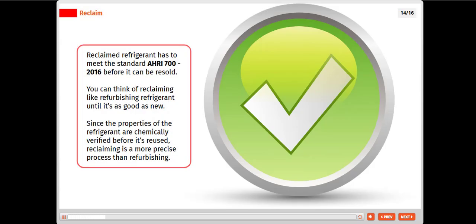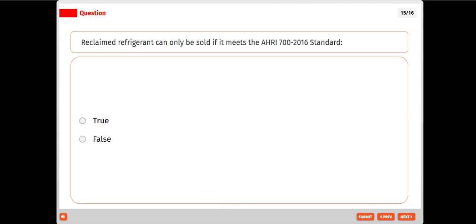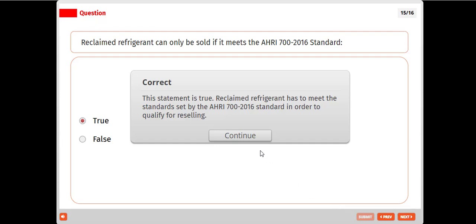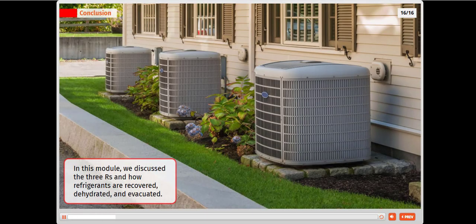Reclaimed refrigerant has to meet the standard AHRI 700-2016 before it can be resold. You can think of reclaiming like refurbishing refrigerant until it's as good as new. Since the properties of the refrigerant are chemically verified before it's reused, reclaiming is a more precise process than refurbishing. Reclaimed refrigerant can only be sold if it meets the AHRI 700-2016 standard. In this module, we discuss the three R's and how refrigerants are recovered, dehydrated, and evacuated.